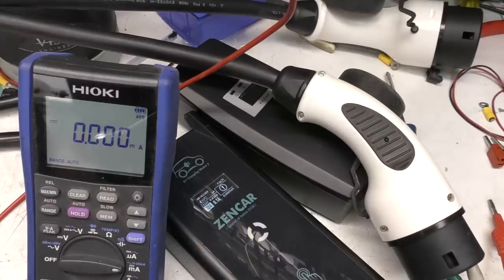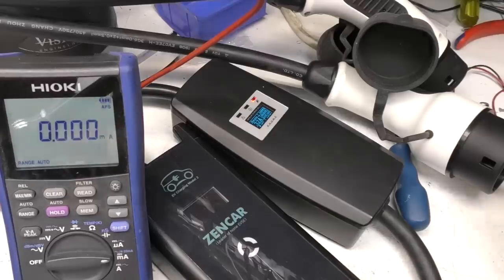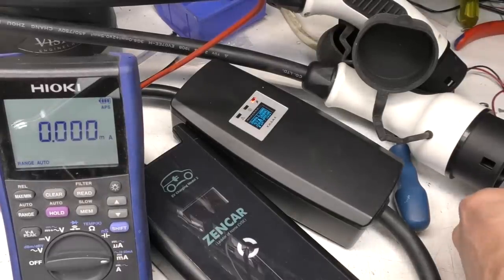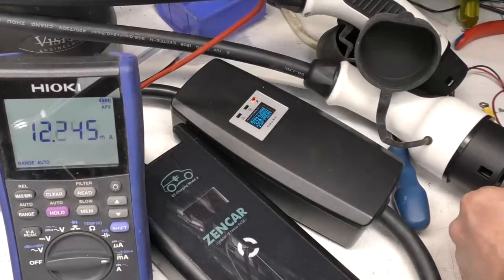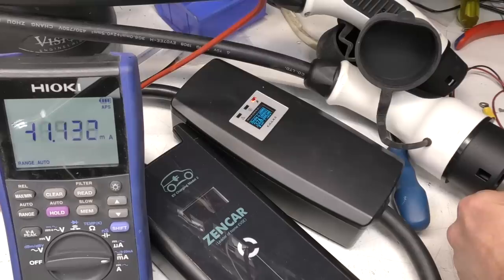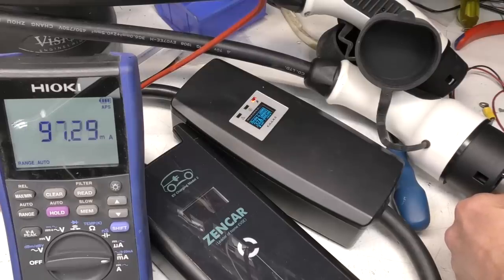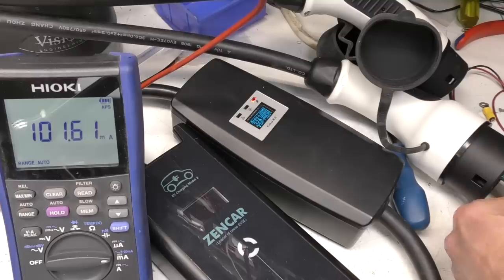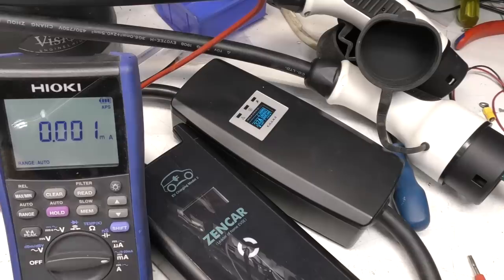but a gradually increasing DC fault doesn't cause it to trip, which is fairly expected because it looks like it's using a normal AC current transformer. And let's check the Khons unit, which I expect to be the same. Yeah, no trip up to 100 milliamps, but probably a trip if I suddenly disconnect it. Yeah. So that's pretty much as expected.